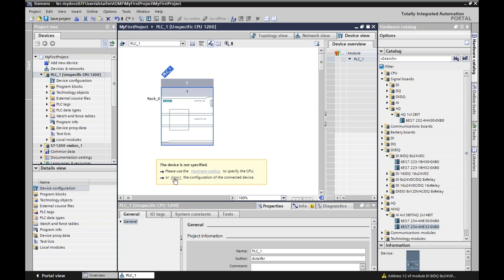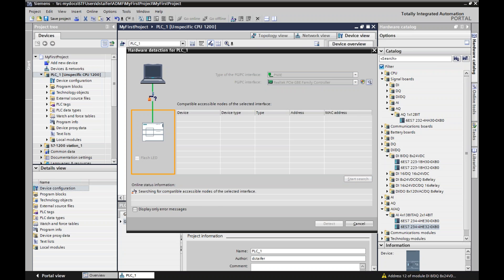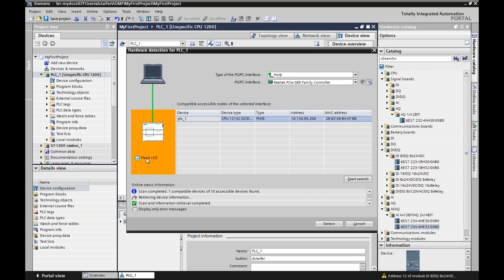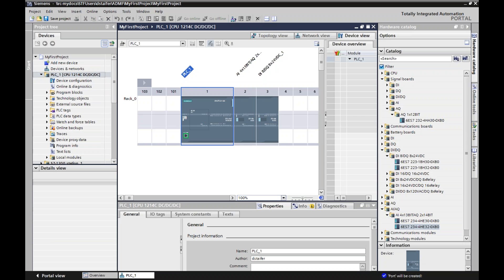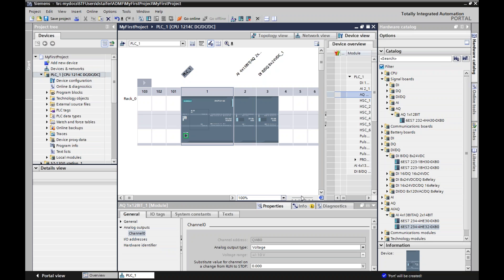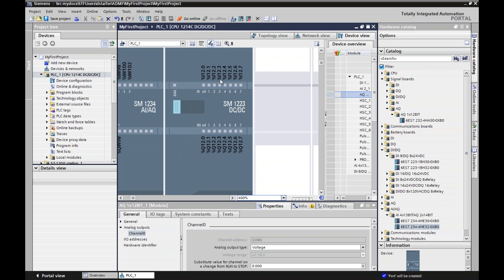I'm going to hit Detect, because this thing is smarter than me and I don't want to disconnect things. It will bring up the communication pathway window that we showed you last time. I start searching for the PLC I want to communicate with. And look — there's my PLC. I can flash my LED to make sure, but that's the only PLC on my network right now. So I'm going to hit Detect. And check that out — does that look familiar, like we just created it? Yes, it does. It has all the hardware and all the I/O.